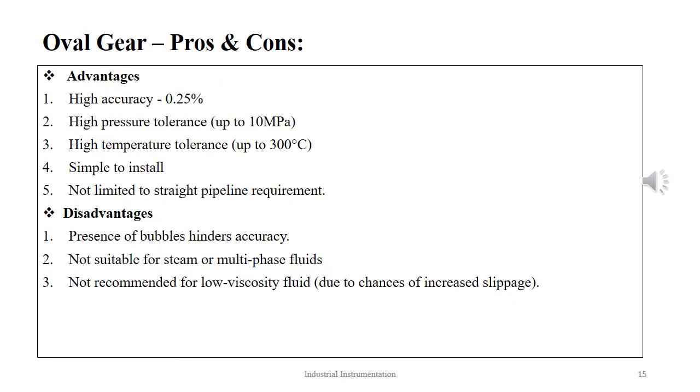The advantages of the oval gear meter are: very high accuracy ±0.25%, very high pressure tolerance up to 10 MPa, very high temperature tolerance up to 300 degrees Celsius, simple to install, and not limited to straight pipeline requirement.